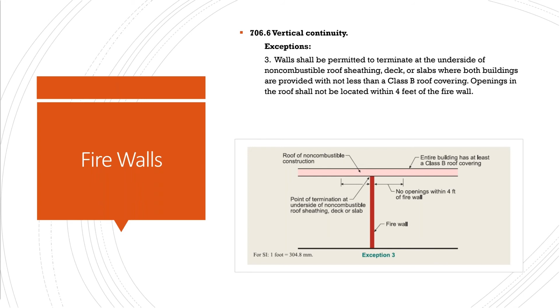And then this is another version of a butterfly condition, but it's specific for buildings of Type 3, 4, and 5 construction. Walls shall be permitted to terminate at the underside of combustible roof sheeting or decks provided. So if you're in the academy, I would say underline for these last two: you want to underline non-combustible in exception 3, and in exception 4, you want to underline combustible. And provided there are no openings in the roof within 4 feet of the firewall.